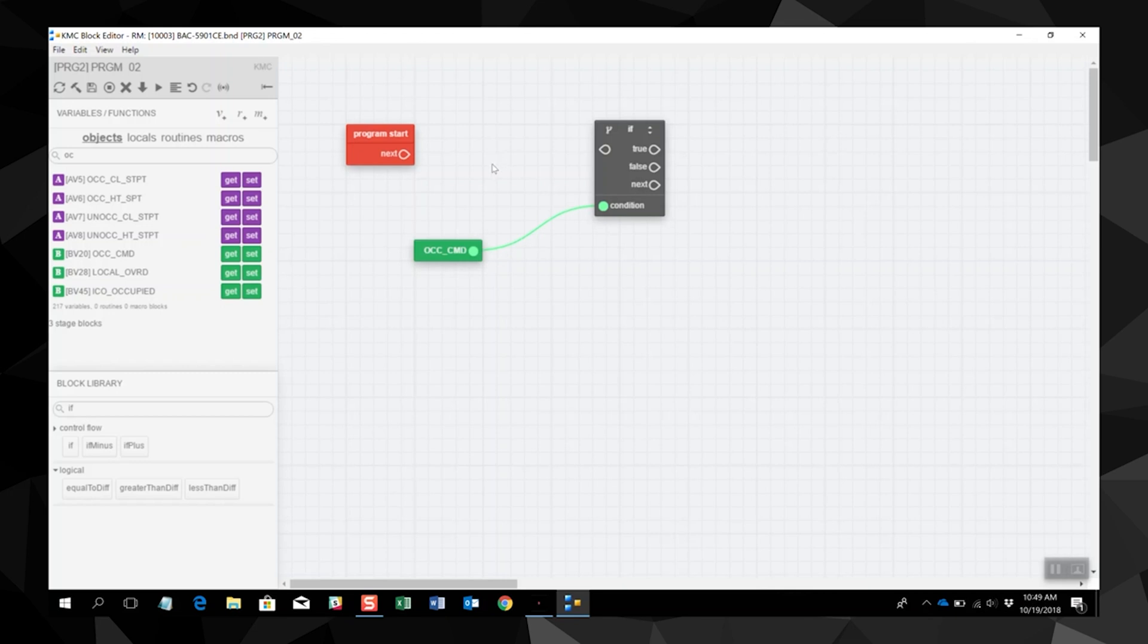We are going to tie our start block in the program into the if block. Now if the occupancy command is on, we are going to start the fan. If the occupancy command is off, we are going to stop the fan.